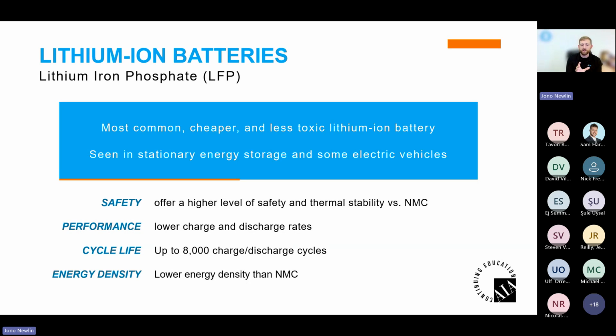So these have 8,000 cycles at like a 2-hour deployment. For example, a 3 megawatt hour container could support 1.5 megawatts continuously for 2 hours, or it could do 750 kilowatts for 4 hours. So the 4-hour metric is going to affect how it degrades compared to the 2-hour metric. You could see 8,000 cycles on a 2-hour metric, and then 10,000 discharge and charge cycles on the 4-hour metric. So it is a little bit lower energy dense than NMC, though that is constantly evolving.